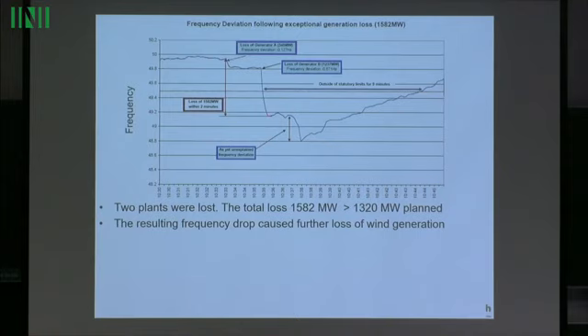Now wind power plants have, or used to have at that time, under-frequency relays, which would disconnect them if frequency is too low, basically to get them off the system, because it's something wrong going on. So when there was not much wind, it was just to get rid of them, because they could cause problems. Now they cannot do it this way because there's too much wind, but at that time it was normal. So here we started to lose wind. So you see frequency was dropping down to 48.8 hertz, which is very, very bad.